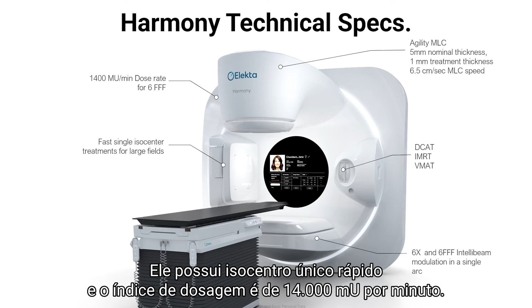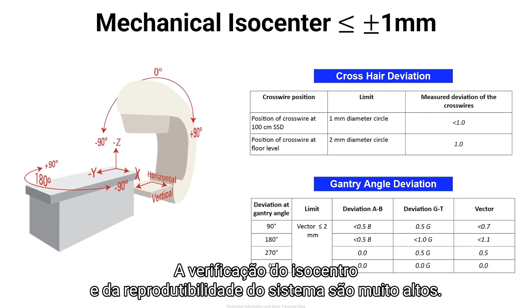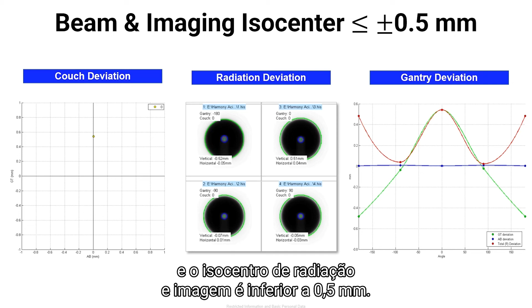So this is our mechanical isocenter limits. As you see, our gantry angle deviations and the cross hair deviations are less than 1 millimeter. So the system's isocenter verification and the reproducibility is very high. And this is the imaging and the beam isocenter coincidence. As you see, it is less than 0.5 millimeter. So in total, our mechanical consistency is less than 1 millimeter, and our radiation and imaging isocenter is less than 0.5 millimeter. So it means that you hit the target, you hit your isocenter without any problem.